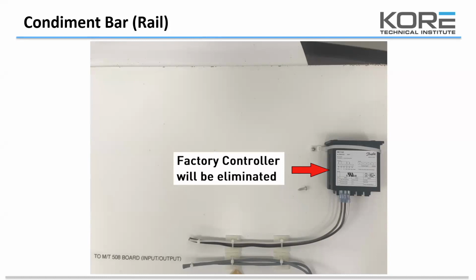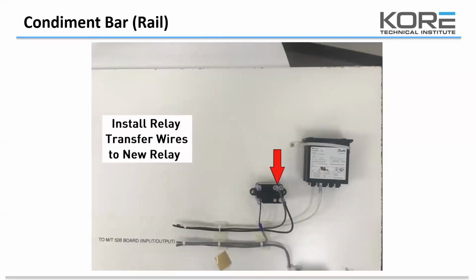All we're doing in this particular instance is we're eliminating the white or the neutral wire, and we're simply taking the black power wire, putting it on 4 for the line in, and taking our brown wire, which is the load side to the compressor, and putting it on 5. There again, making it fail in refrigeration mode. Also in this one, we are removing the temperature probe that goes up to the well and putting our own slab temperature probe in its position.